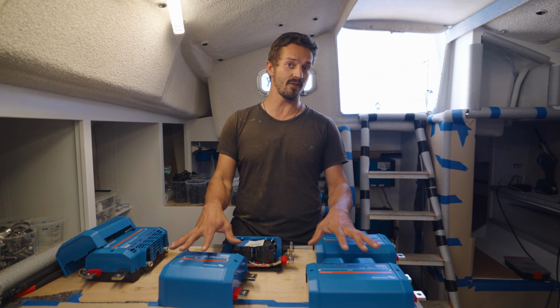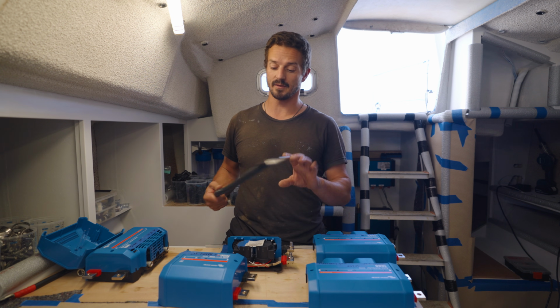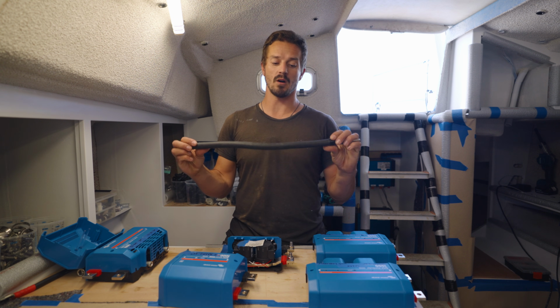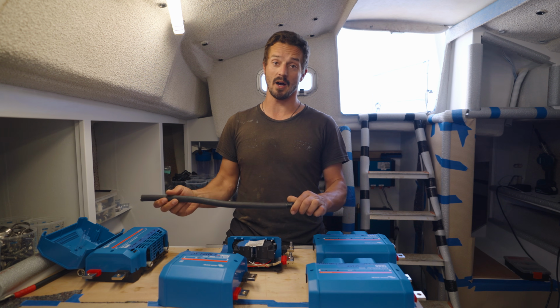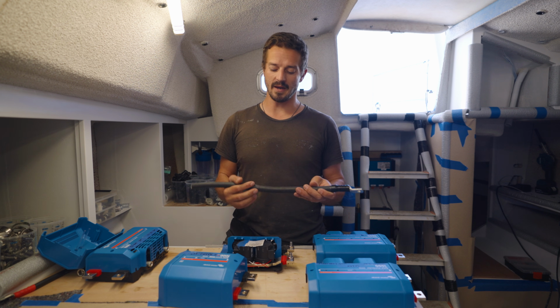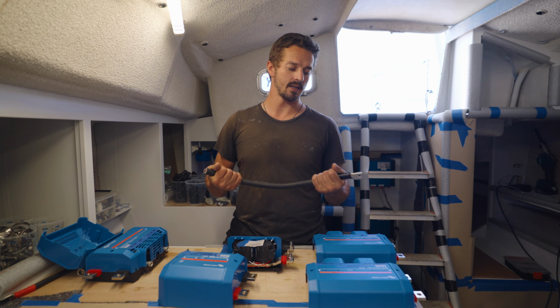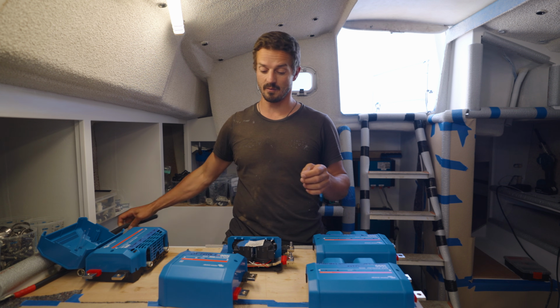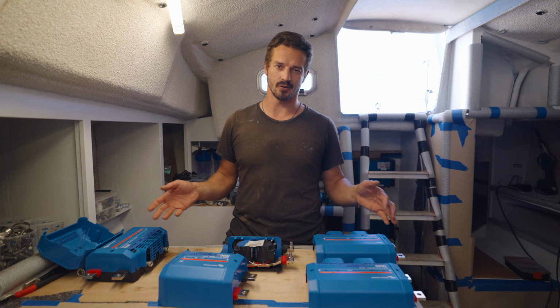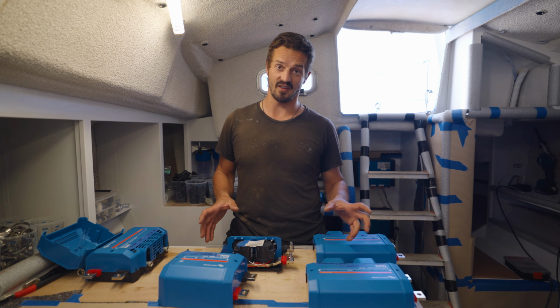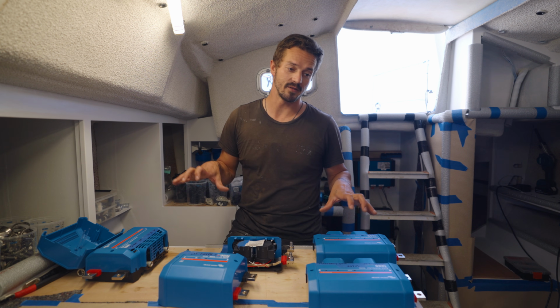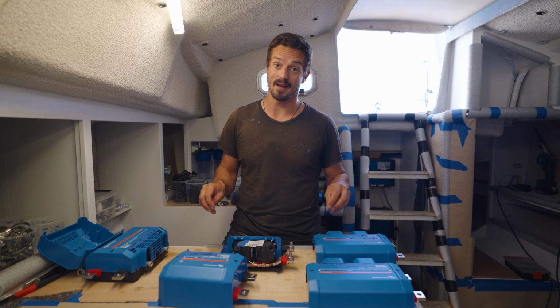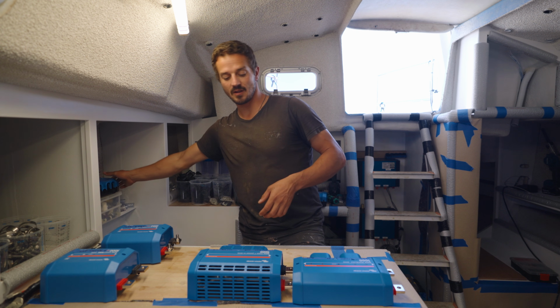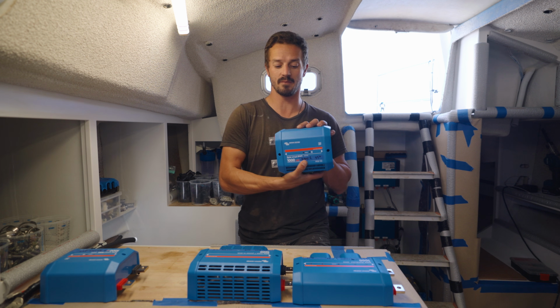Technically you can definitely wire each box individually - that's not an issue - but then you have to run cables between each of them. Because we're running a 1000 amp system, that would mean running four big chunky cables between each box, which would be pretty messy, complicated, and add a bunch of extra weight. So we're going to do our best to bolt them all together as they're designed to be, and find a place to fit them, though we do have some planning to do around that. Originally we had plans to have each of these individual BMSs.